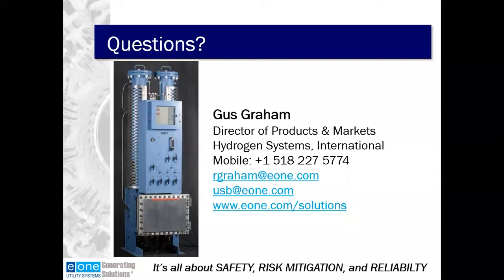Okay, another question has come in. What to do if the generator dryer is under maintenance or under regen, say 4 hours, and a leak happened? I'm not sure I fully understand the question, but I'm pitching it to you anyway, Gus. Well, if it's referring to a leak of water in the generator, again, the regeneration process is occurring concurrently with the tower being in service, so it'll continually be drying the generator. So if they're referring to a leak of water into the generator, we'll be able to remove that water, up to a certain point, depending on how big the leak is, because the regeneration process doesn't stop the drying process. We have the two towers for that reason. One is always in service by design. The second one is maintenance.